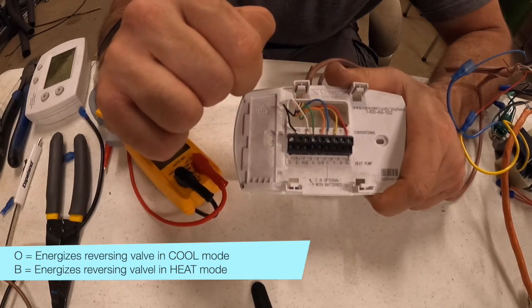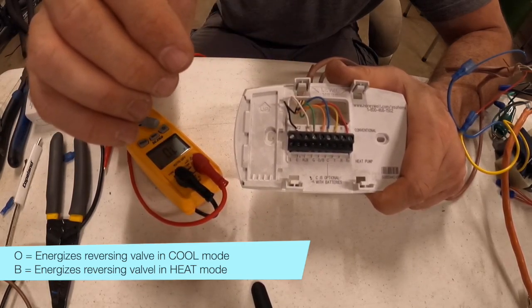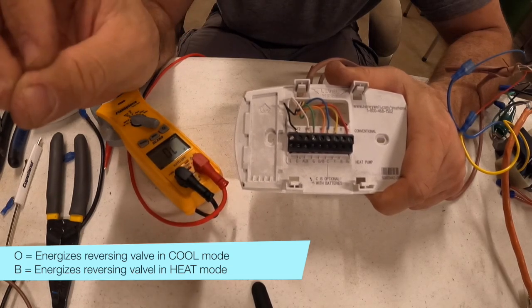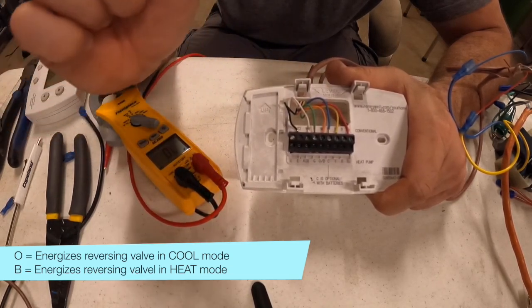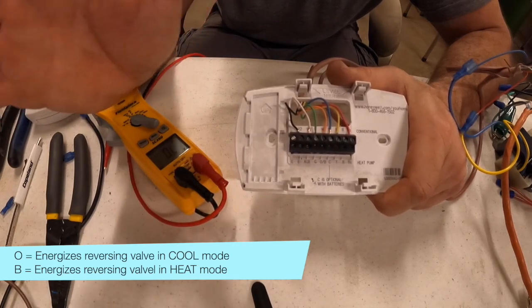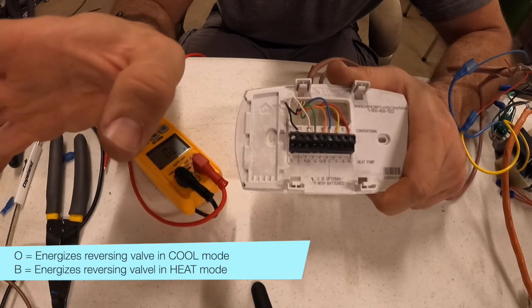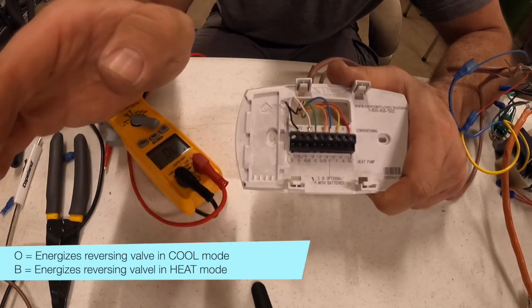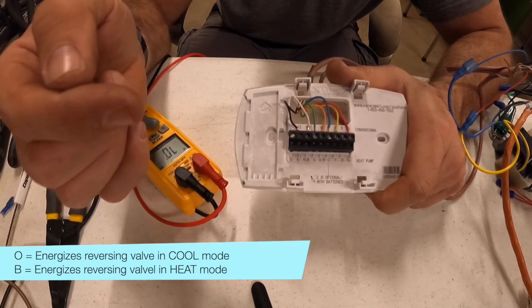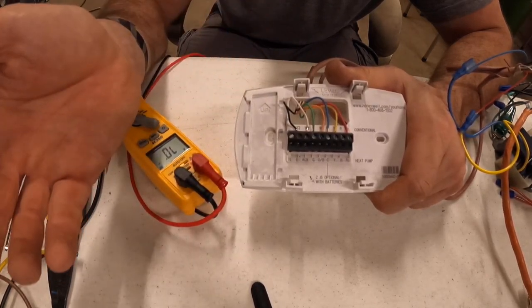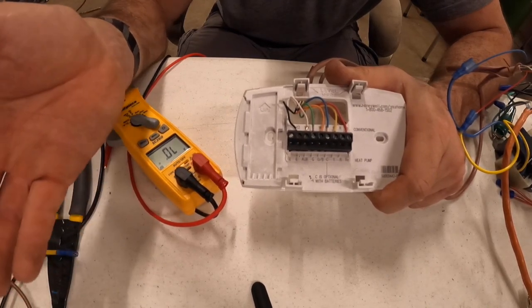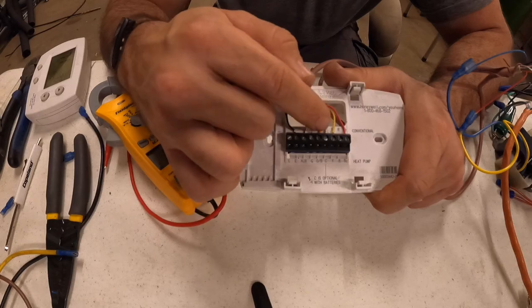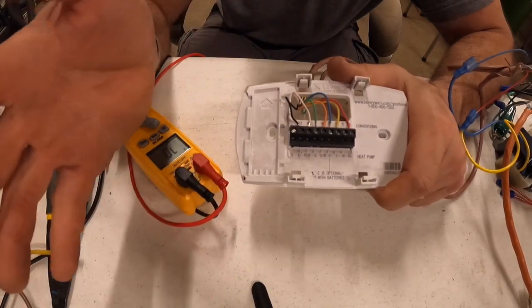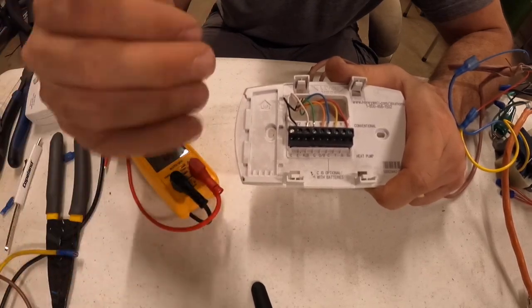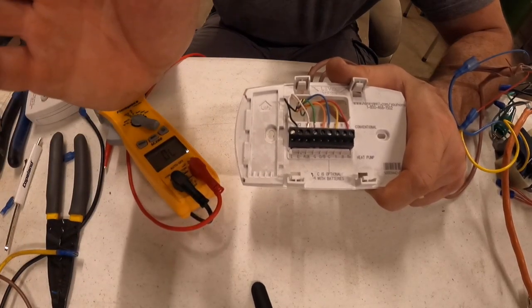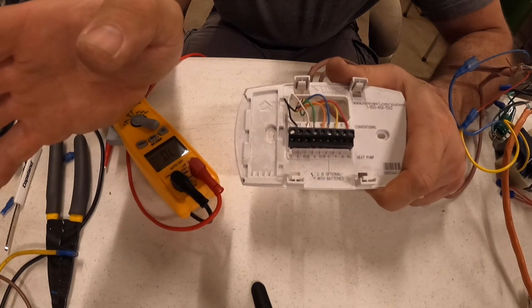On the other hand, for Rheem and Ruud, the B terminal or B designation means that when there is a call for heat, it sends the voltage to that reversing valve. So the opposite is true for O. When you're calling for heat, there is no voltage sent on the O terminal, because that means it would be in cool mode for O, and the opposite is true for B. So with the B designation or Rheem Ruud, when you're calling for cool, there is no voltage supplied to B. It's the same thing. O and B just designate whether or not you're energizing that terminal in cool or heat.